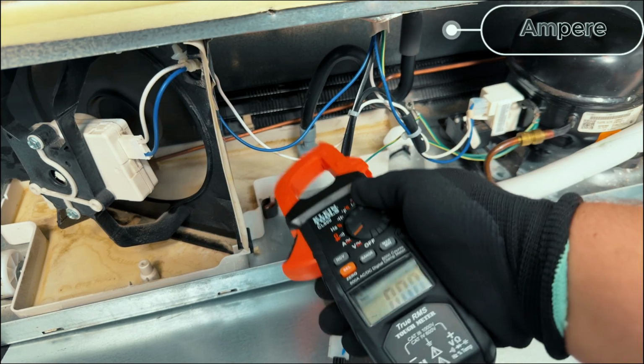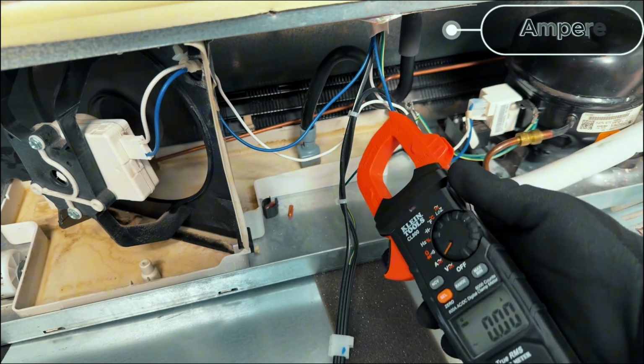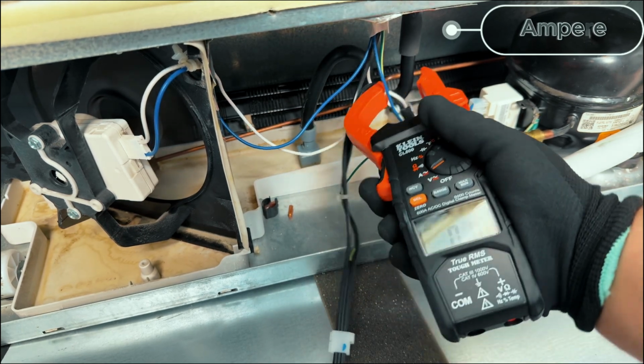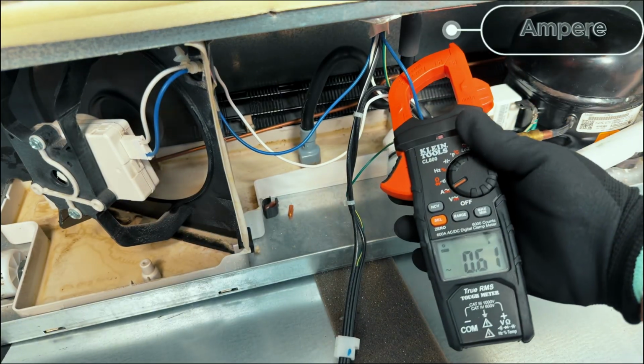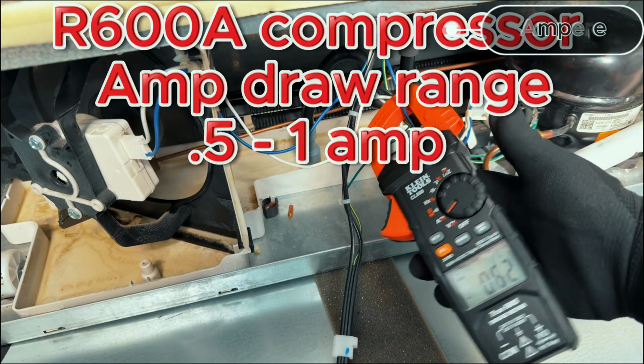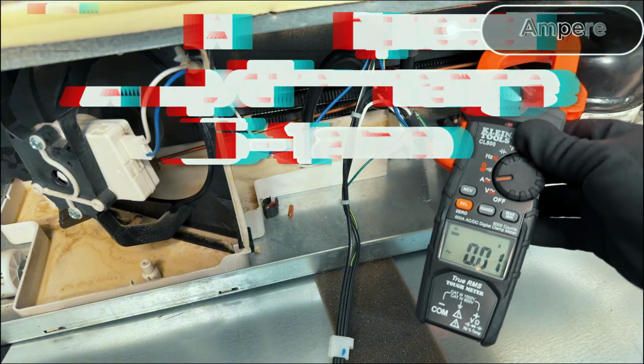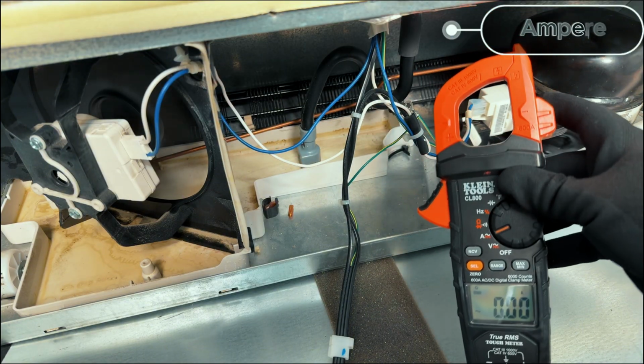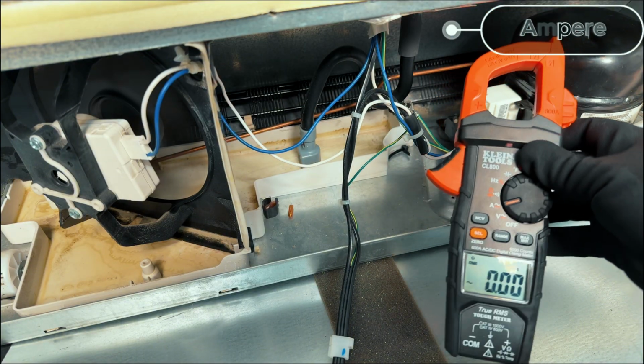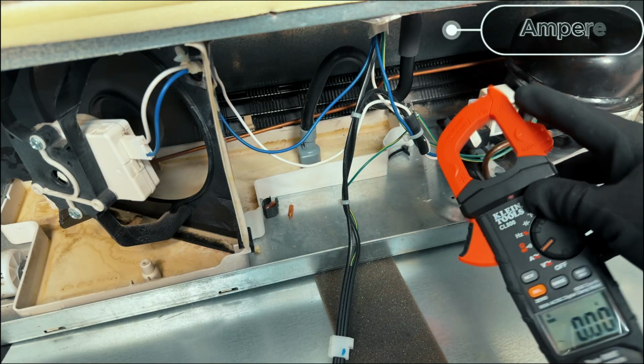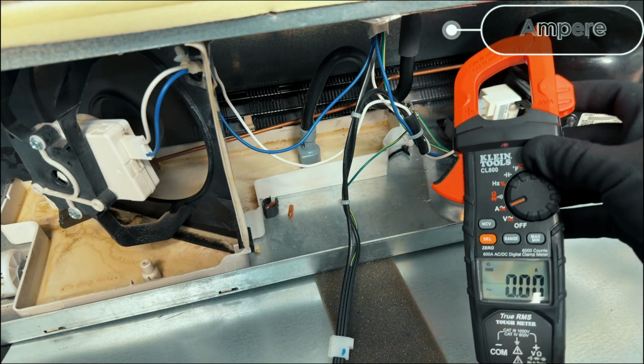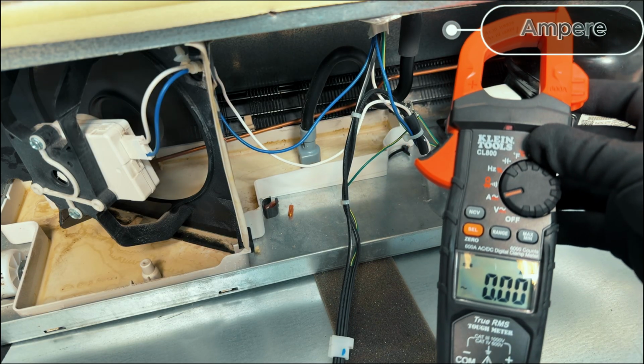So again, you never want to check your common wire, you want to check line. And so I can go right back to the line here, check it again, 0.6 amps. And that's the easy way to check amp draw. You just want to be on a live power wire going to your load and clamp just that one wire inside your clamp and make sure that you have the correct set. And that's it.